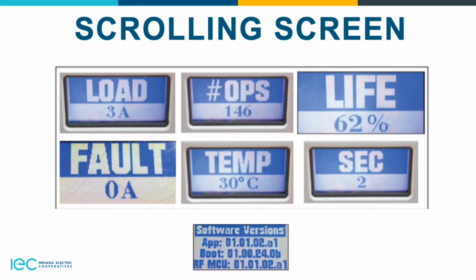This screen shows some optional screens that you can put in your settings. You can have your load, which is showing 3 amps, and your fault magnitude, which is measured in amperes if it is below 1,000 amps. It's kiloamps if it's above that. On your ops counter, it tells you how many operations it's dropped open. Temperature is measured in Celsius. Your life is your contact wear on the device.